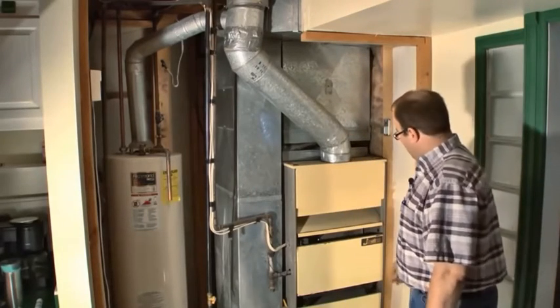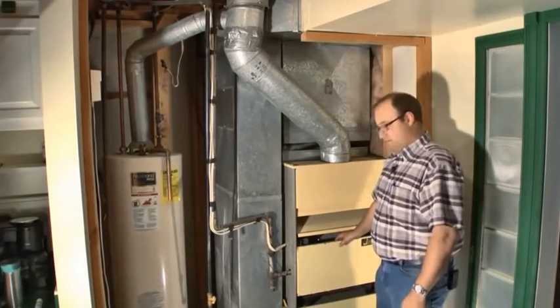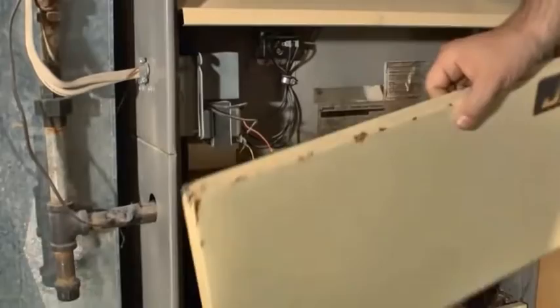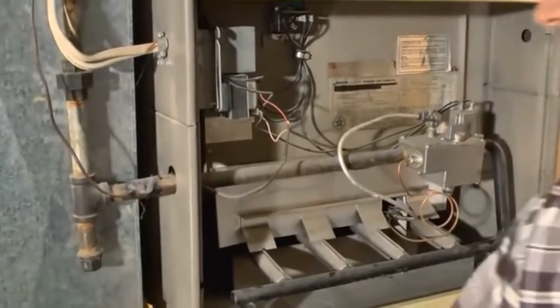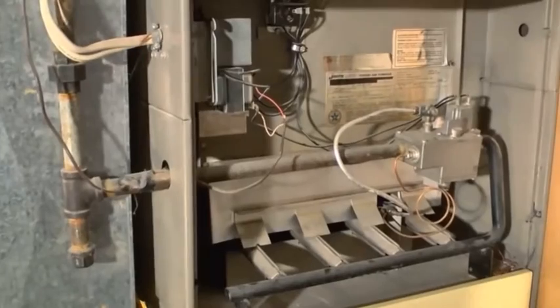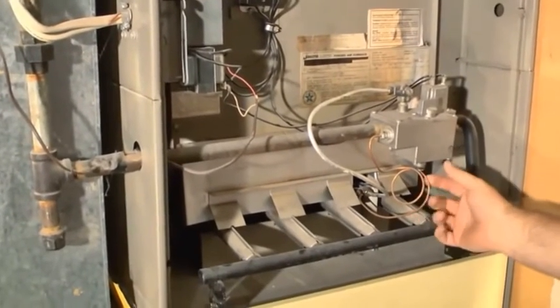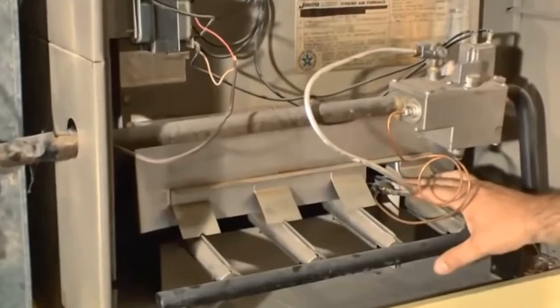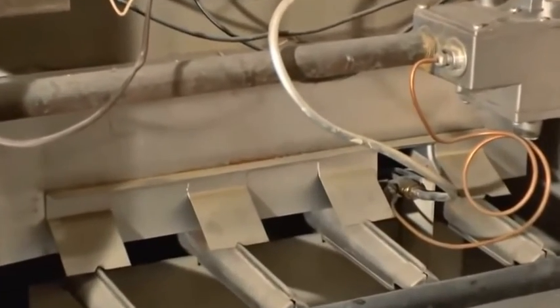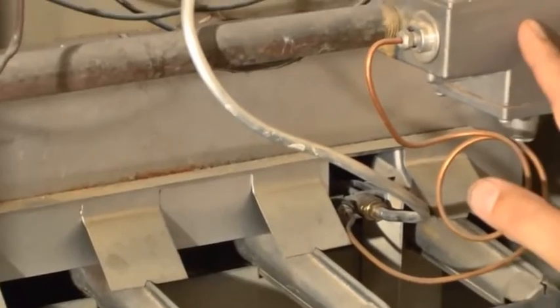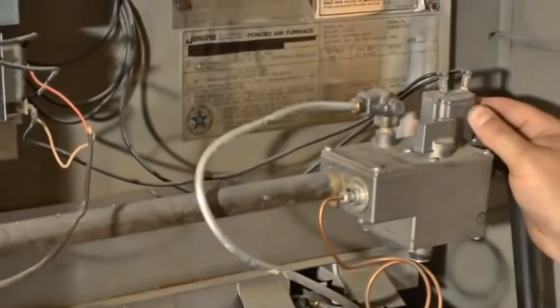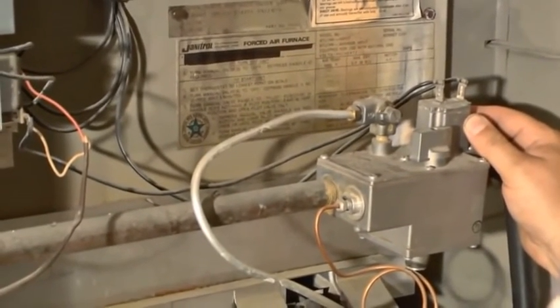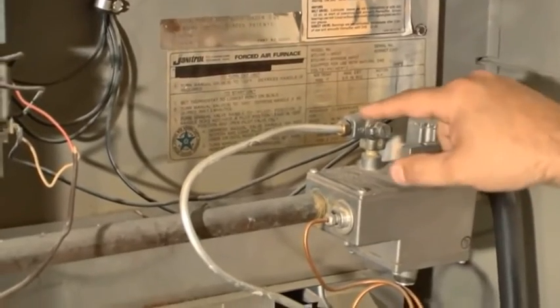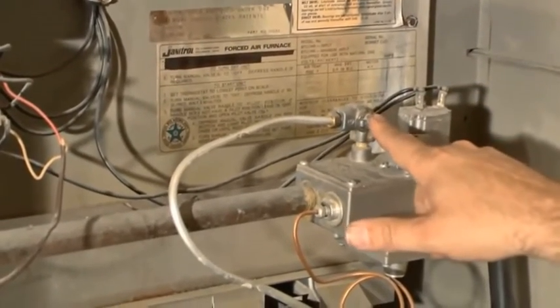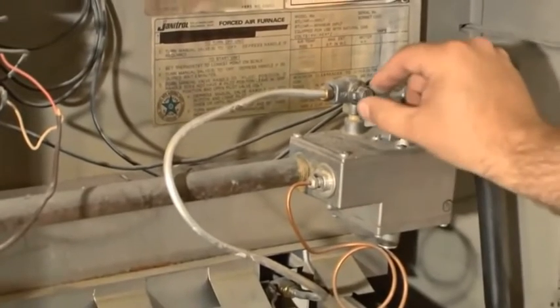The next step is I usually just open these up and take a look at what's inside. Okay, so we'll take a look at what's inside this unit. This is a standing pilot furnace. Here's the thermocouple. Inside here I can see that the pilot's lit. Here's our gas valve. Looks like this is a 24 volt gas valve, natural gas. We do have the ability to shut the gas off to the pilot with this manual valve right here.